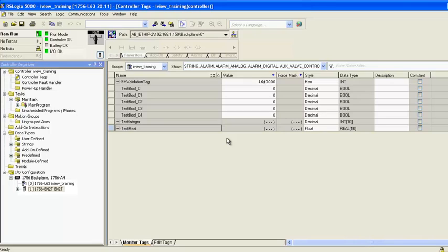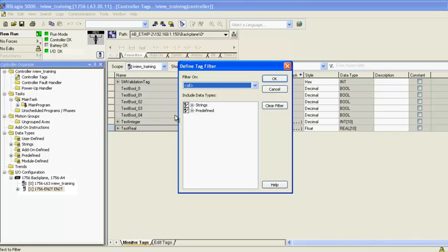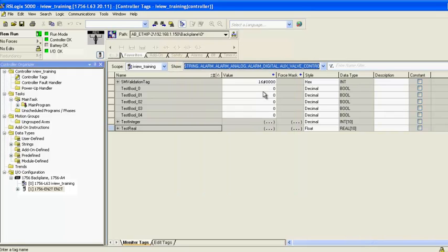Once online, I can see solid green for Run Mode, Controller, and I.O. In the Controller Organizer tree, I'll open up the controller tags. I'll click on the Show drop-down menu, select Configure and verify that all tags are being displayed, which is indicated by the checkmarks in the box. If you do have to select additional display types, just click OK when you're done.